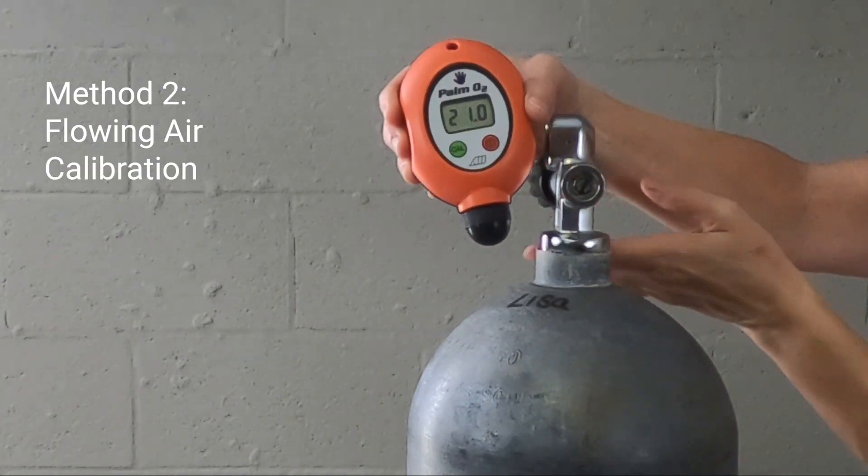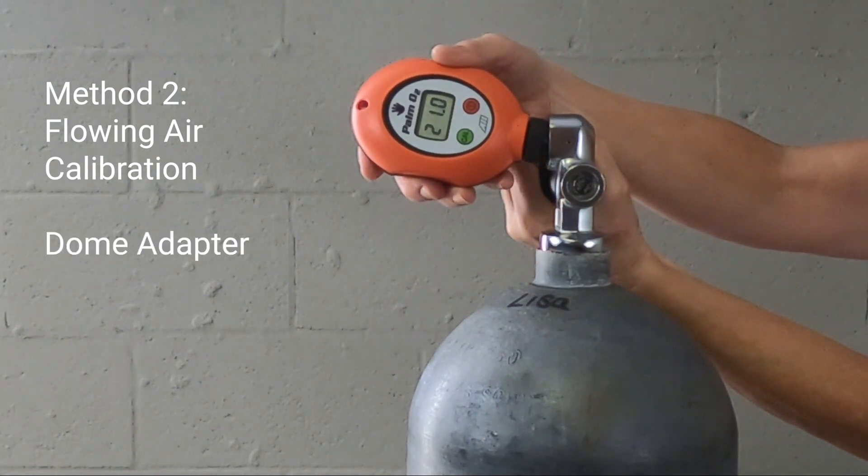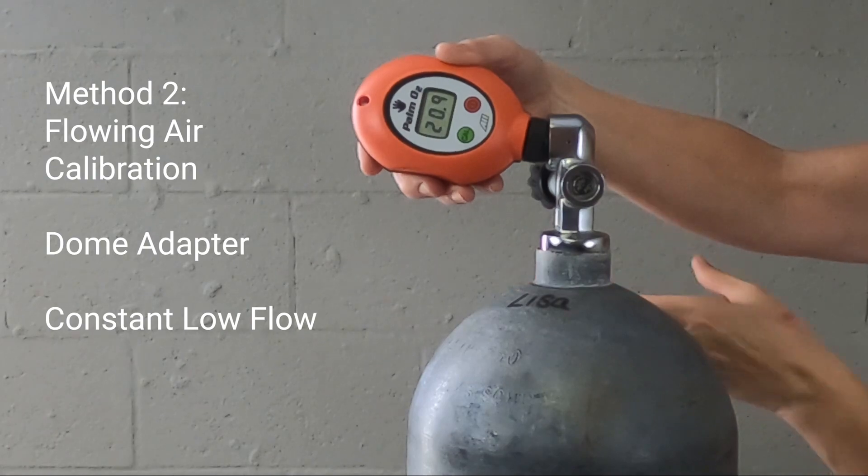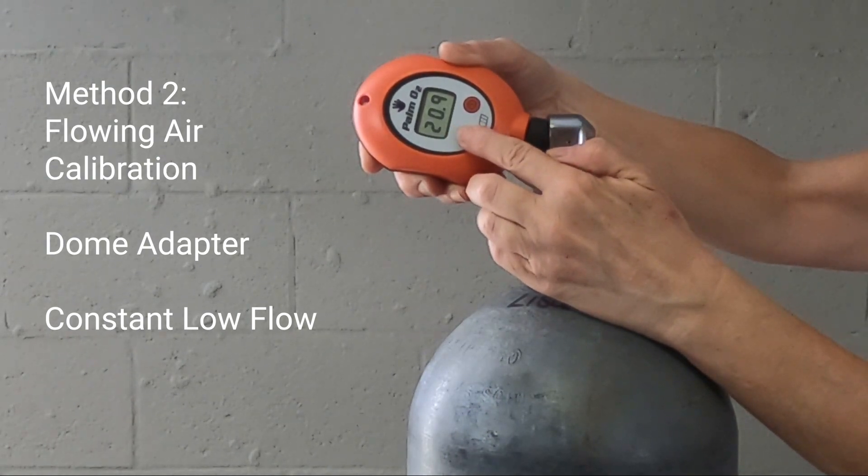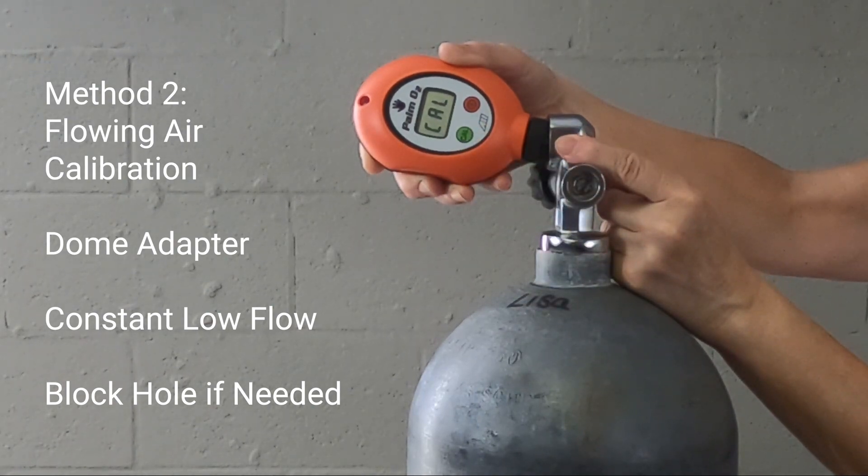Using method two, we calibrate with flowing air using the included dome adapter. Open the valve just enough to get a constant low flow of air. If the DIN outlet valve design includes a tiny hole on the side, hold your finger over the hole.